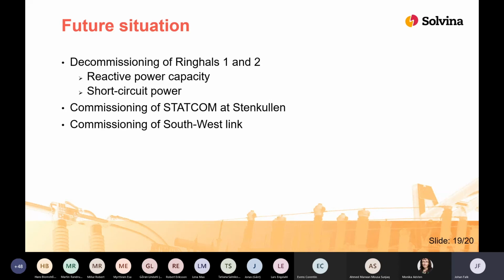The decommissioning will also affect the short circuit power by reducing it. And we have talked a bit more about this short circuit power in the report, but reduction in short circuit power in short makes the area more susceptible to voltage changes. The commissioning of the StatCom at Stenkullen will add about 200 megavars and will surely be a great resource for these aspects. Also, the commissioning of the Southwest link will aid.